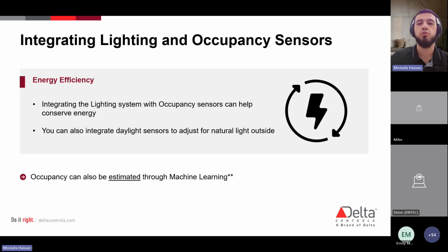This is, of course, great for energy efficiency, right? An example of a sequence of operation for lighting integration with occupancy: all the lights are off when the space is unoccupied. If the occupancy sensor detects movement, it sends a signal to the lighting control system, and then the lighting control system will turn on the light to a predefined level, 0 to 100, that can be proportional as well.